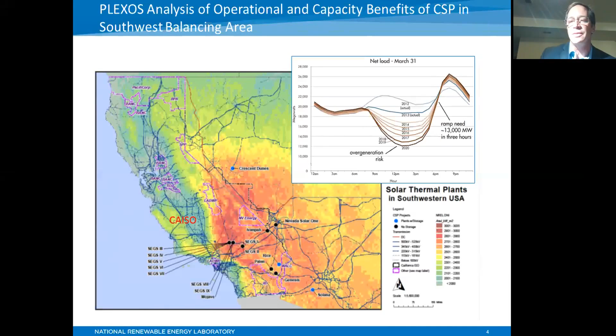What is the amount of thermal energy storage on the system? And the second one is, what is the solar multiple for the CSP configuration? The solar multiple is the size of the solar field relative to the size of the turbine. The higher the solar multiple, the higher the capacity factor of the CSP plant. A low solar multiple is more representative of a peaker plant, while a high solar multiple approaching 2.7 or higher is representative of a baseload plant.